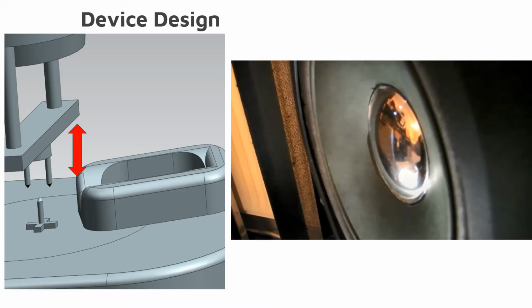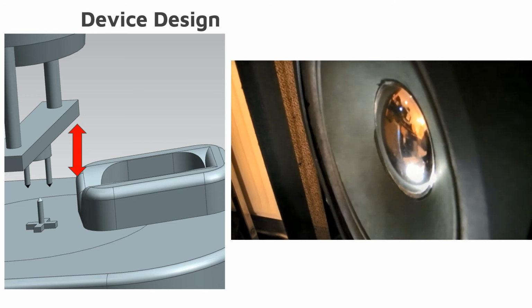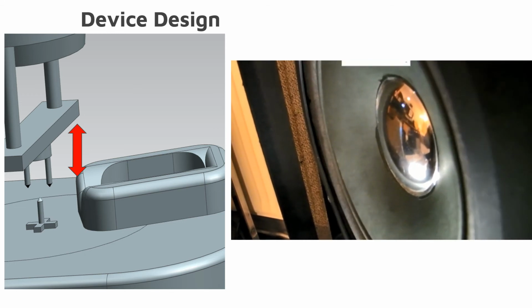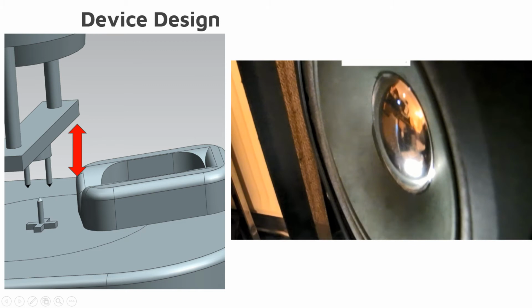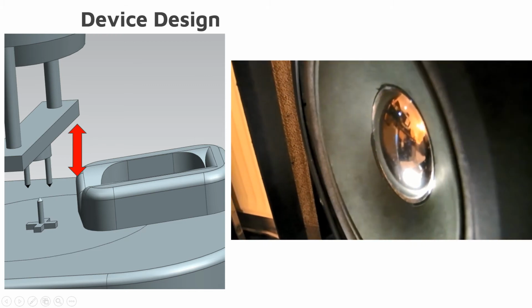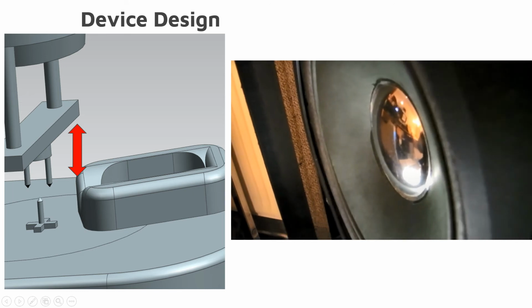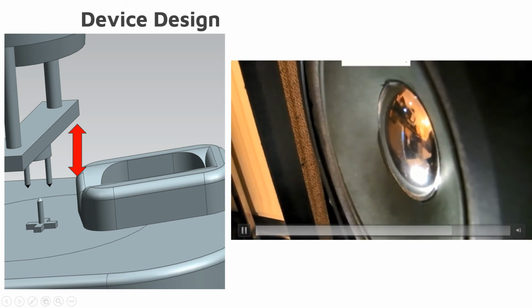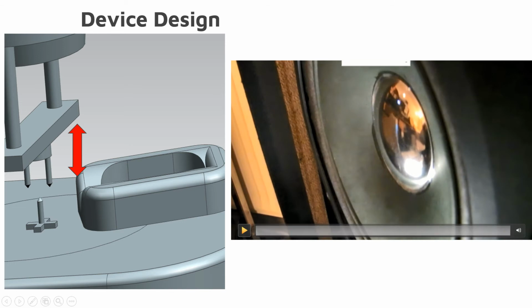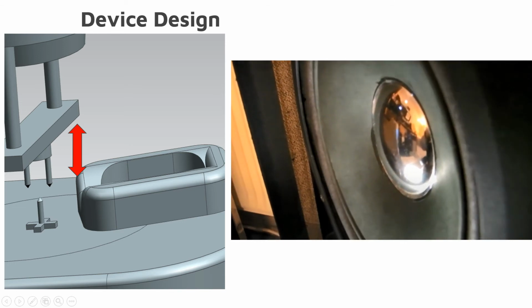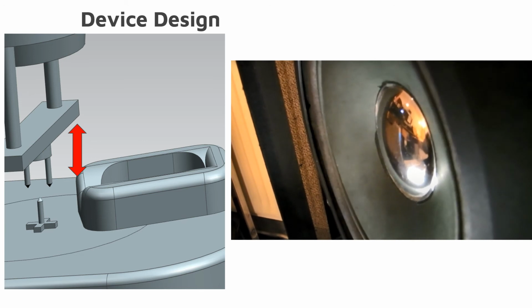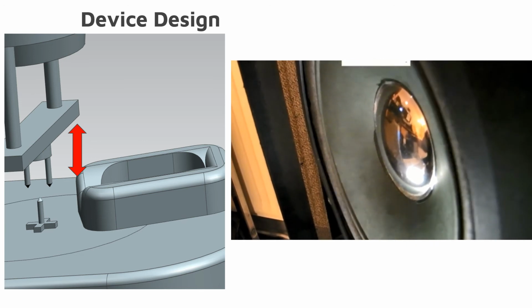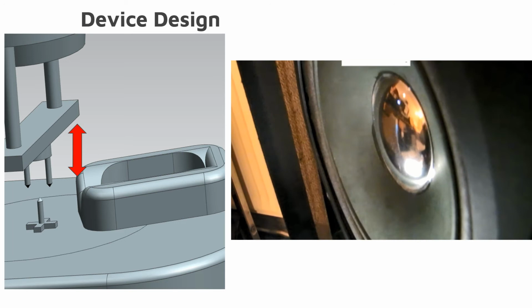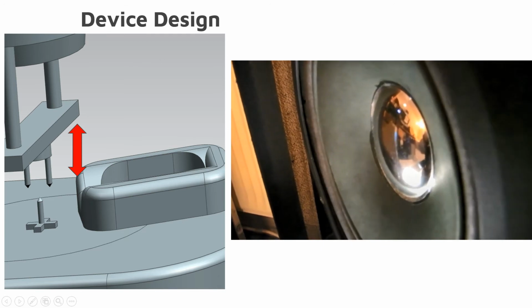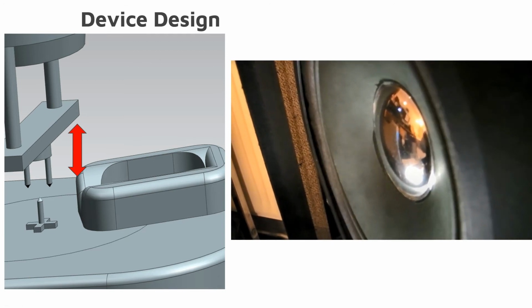As the speaker cone moves, it applies a downward force to actuate the loading arm onto the mouse tibia. The cyclic loading will be comparable to the force while walking. The speaker cone is secured to the loading arm, which is precisely calibrated for frequency, displacement, and force, which are measured and tested using an Arduino program, height and dial gauges, and a load cell. The frequency, displacement, and force can be optimized to fit a specific research requirement.